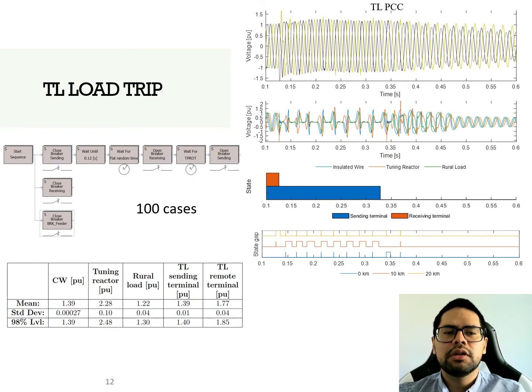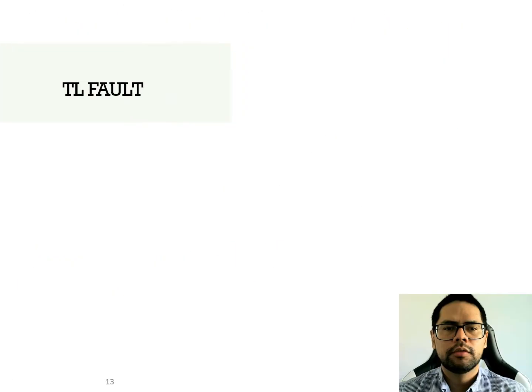When the transmission line overvoltage damps, the gap extinguishes, and after that we can observe the transmission line voltage damping ramp. After 5 cycles, the voltage along the feeder presents a sinusoidal form again. So fault occurrence on the transmission line is a severe condition as the collector line induced voltage can reach very high values. Knowing that the induced voltage depends on the transmission line phase voltage, it is expected that overvoltage on the transmission line will raise the collector line voltage.